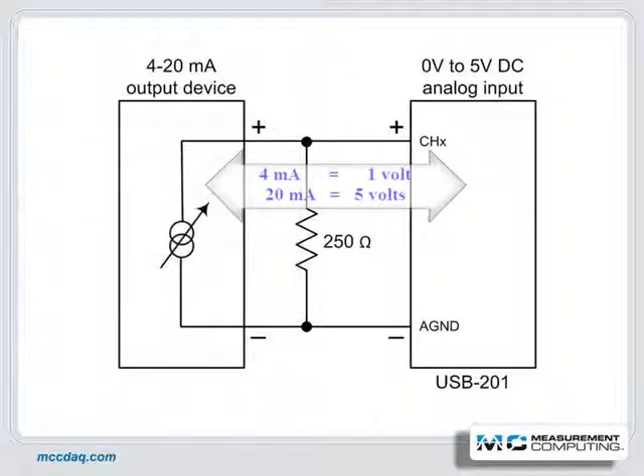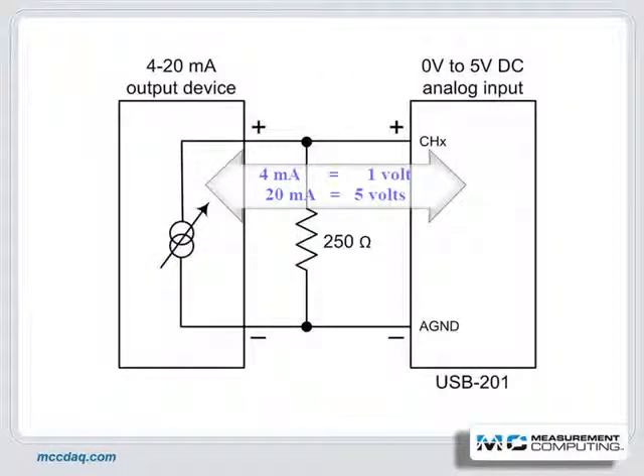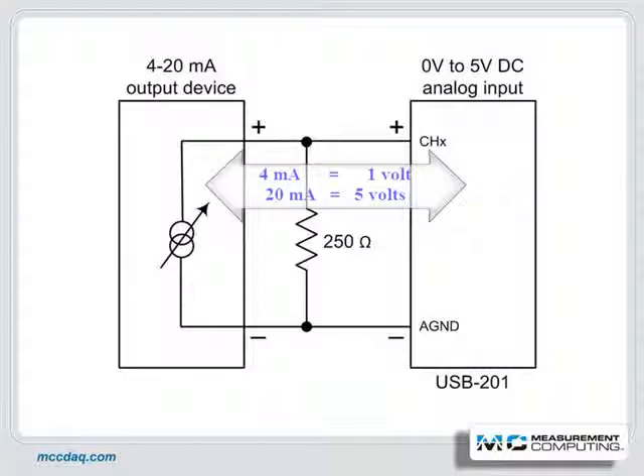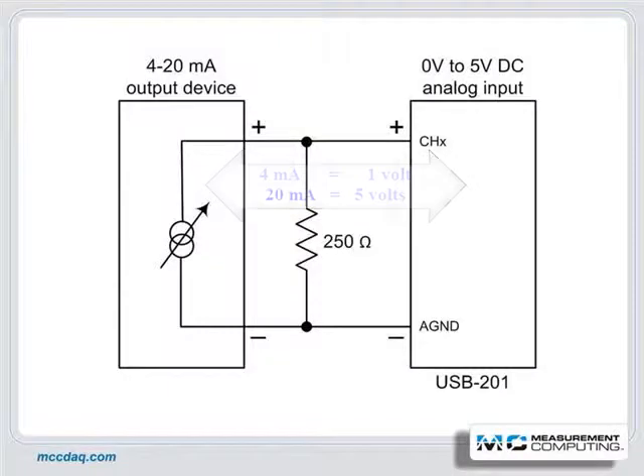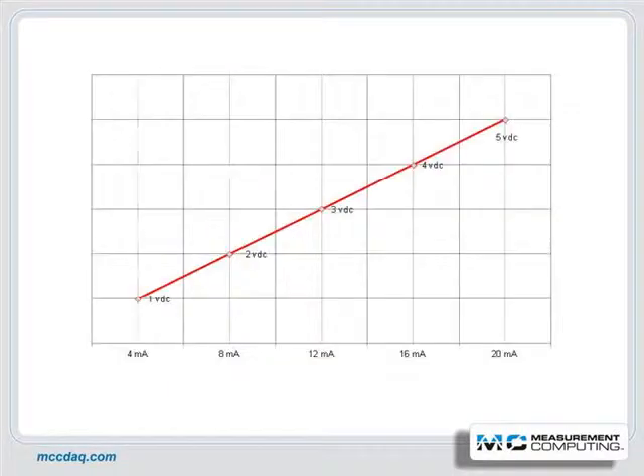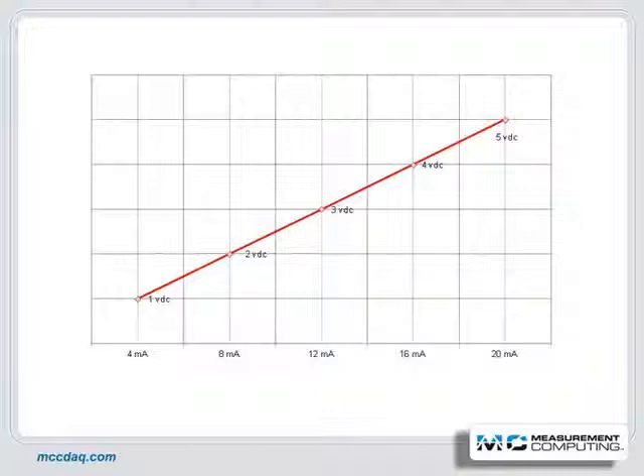Now when your transducer outputs 4 milliamps, the USB-201 will register 1 volt. And when your transducer outputs 20 milliamps, the USB-201 will register 5 volts. The data in between will be linear throughout the entire range.